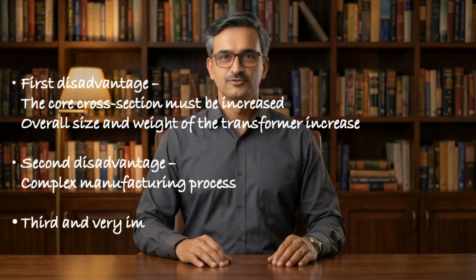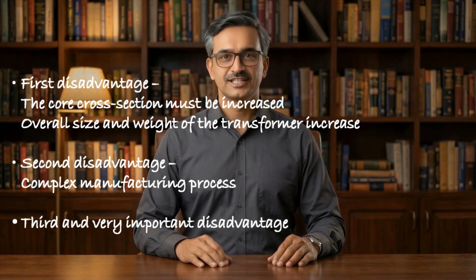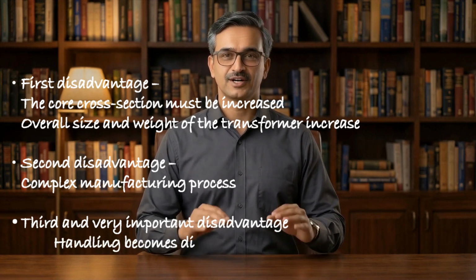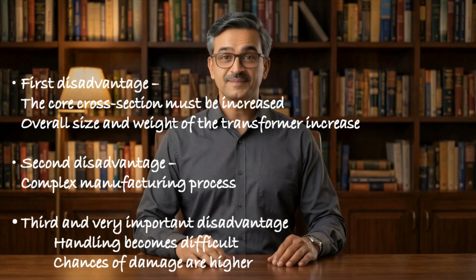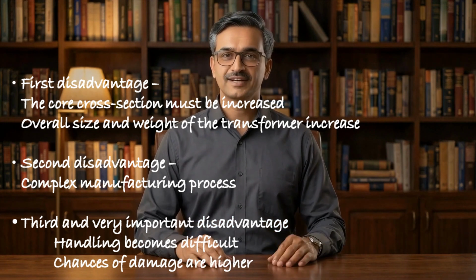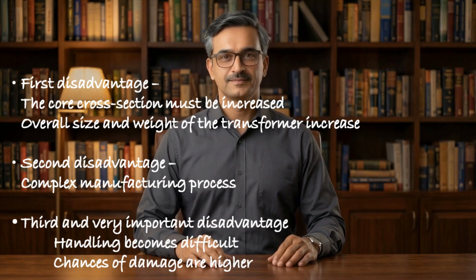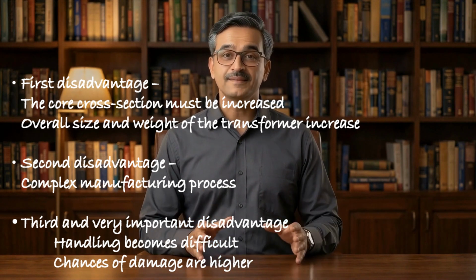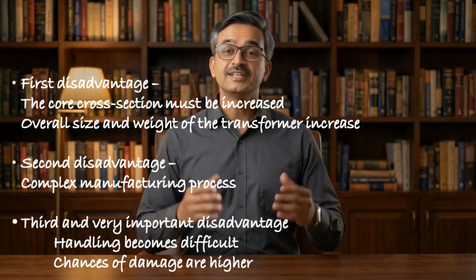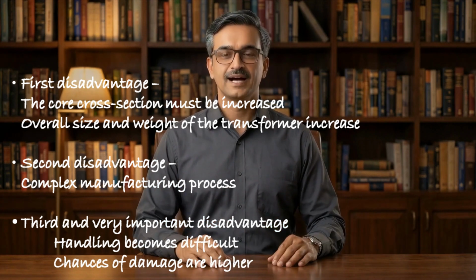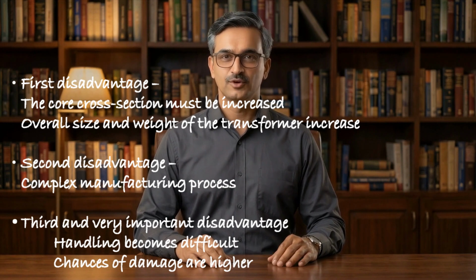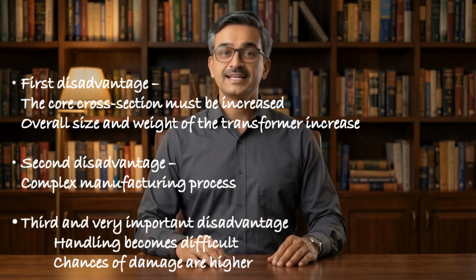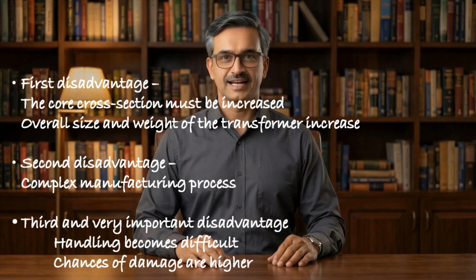Third and very important disadvantage. An amorphous core is very fragile. Very fragile. So during manufacturing, handling becomes difficult and chances of damage are higher. Because of this fragility, it may also affect the long-term durability of the transformer. Now let me add one more important point. Till now, amorphous cores are mainly used in distribution transformers. But for large power transformers or substation transformers, we still use CRGO steel. Why? Because manufacturing a large core using fragile amorphous alloy laminations is extremely difficult and not yet practical.